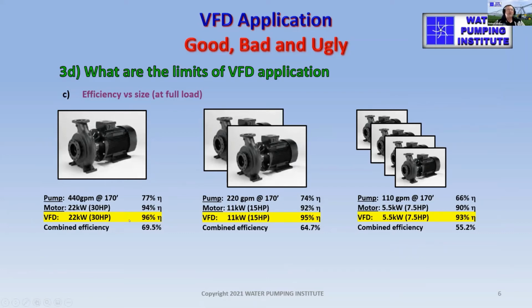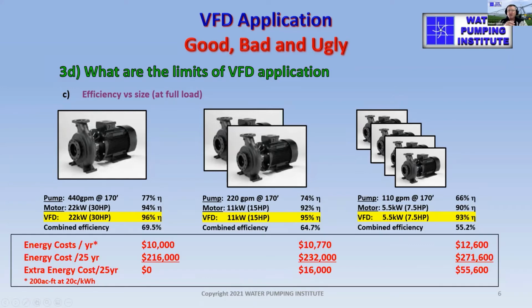So 22 kilowatt, 96%, 11 kilowatts, 95%, or 15 horsepower, 7.5 horsepower, only 93%. But have a look how the motors and pumps themselves vary in efficiency, quite considerable. So the combined efficiency, is the bottom line, is a significant difference, drops from 69.5 down to 55.